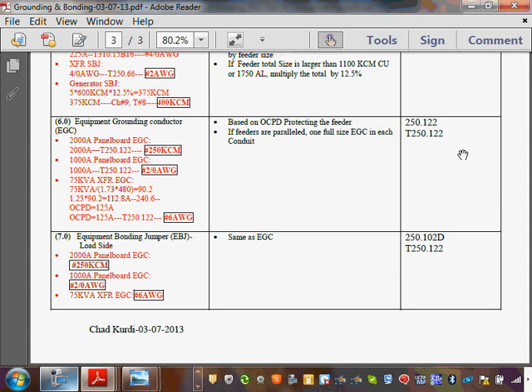If you have PVC, what happens? Do you need to bond the PVC? No. If we have PVC conduits coming, of course, we don't have to bond. If you're coming with 2-inch, 4-inch, 6-inch rigid into a conduit, and there's metal to metal contact between the two of them, then 7.0 does not exist. For most of the applications, 7.0 does not have to exist. In 208/120, 240/120, single phase and 3-phase, the lock nuts will get you there. And threadless or threaded lock nuts will get you there.